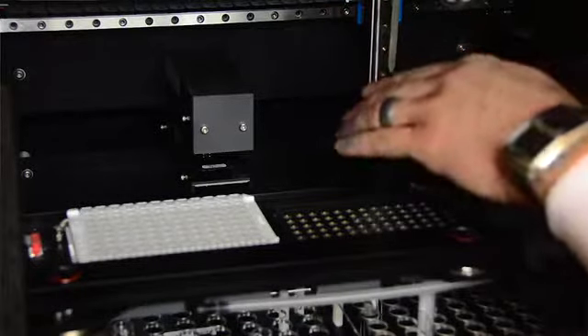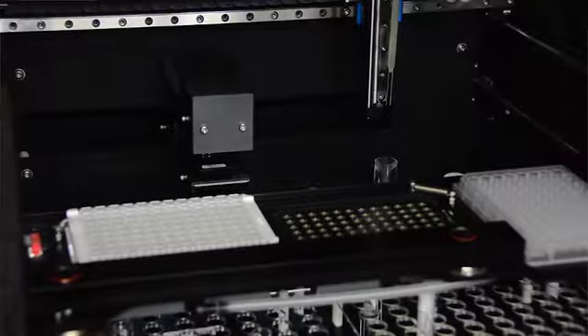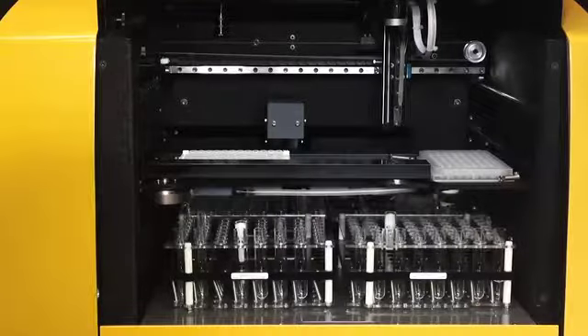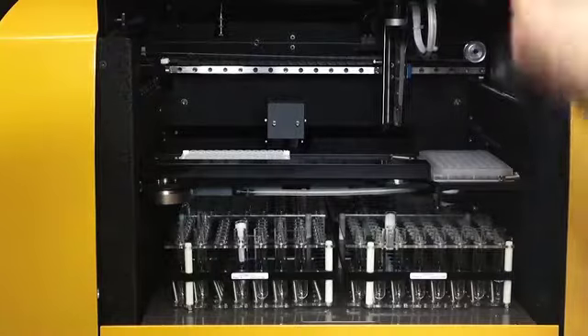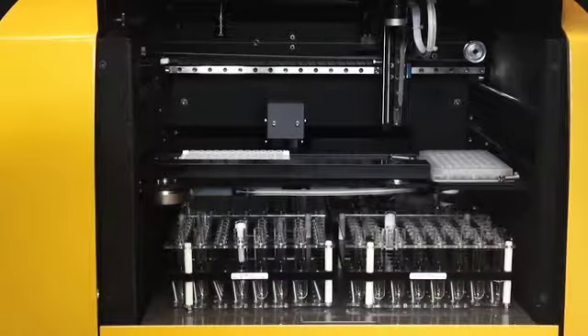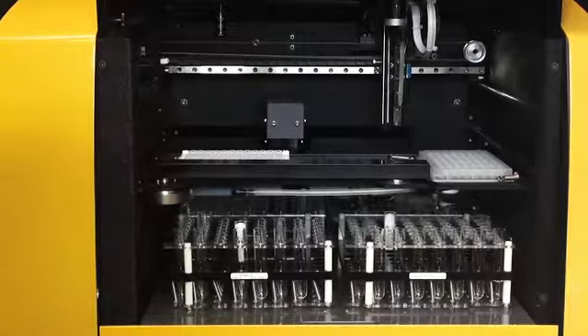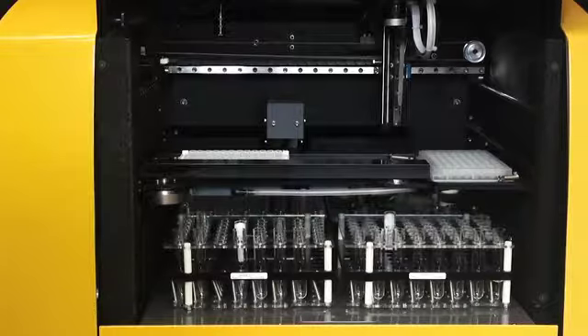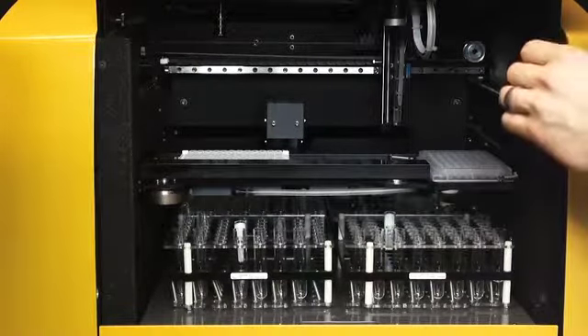But like I said, it's an LED reader, and the main key things with LEDs is that they're faster to switch on and off. They last much, much longer. You're dealing with photons, not heat and light being produced by heat. You're actually dealing with photons, so they need a lot less energy to generate the light. So they pull less energy, they last much longer, they're more robust, and they're faster switching on and off. And that's how we can quickly read 2 plates well by well. Once again, there's 5 filters on every single reader.